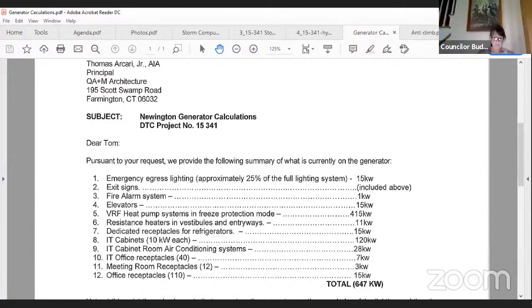They are very efficient. They have the ability to move refrigerant and heat around the building, but at a very low, cold temperature, they basically are electric heat. So when it gets down to a very low temperature, it's mostly electric. So that's 415 kW. So that's why the generator is so large. So even with just that alone, you still need a 400 kW.